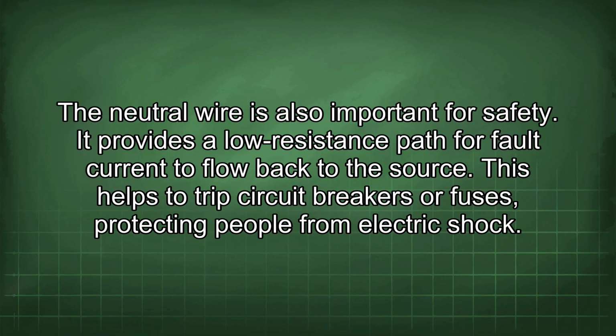The neutral wire is also important for safety. It provides a low resistance path for fault current to flow back to the source. This helps to trip circuit breakers or fuses, protecting people from electric shock.